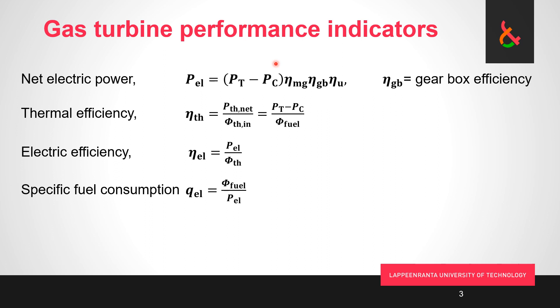And then that net thermal power we multiply first with the turbo generator electromechanical efficiency, then we have the gearbox efficiency because very often our shaft is turning a whole lot faster than the 3000 rpm that our generator wants, and finally we have the transformer efficiency.